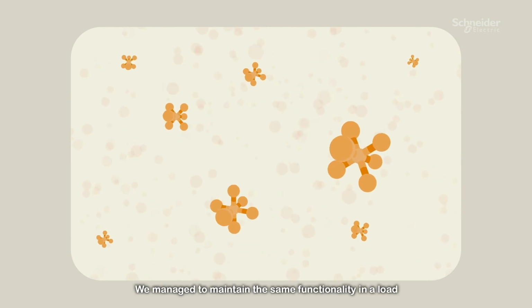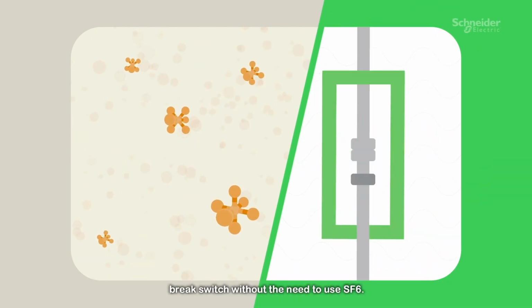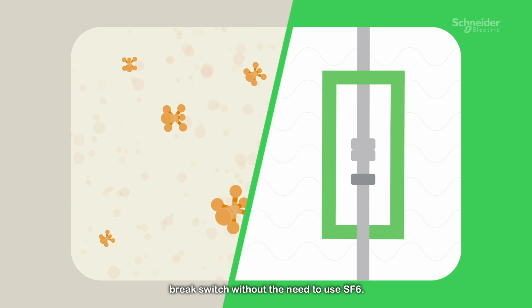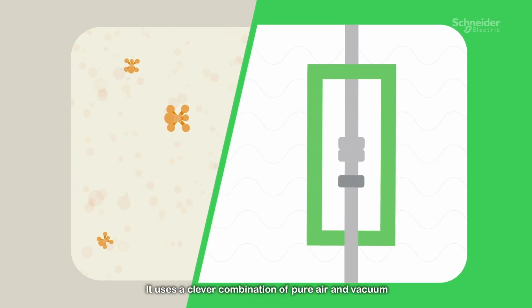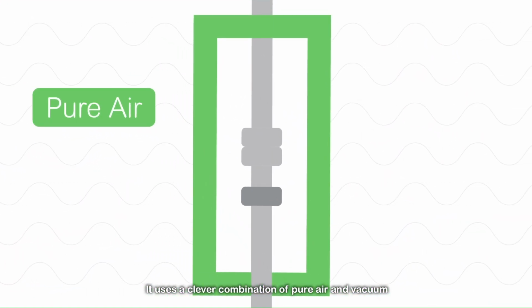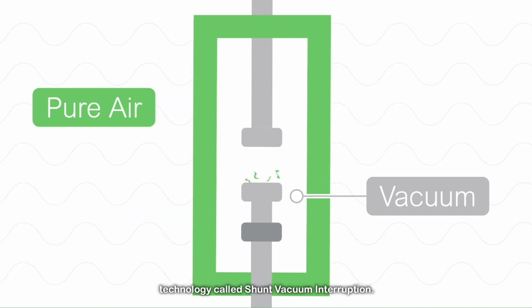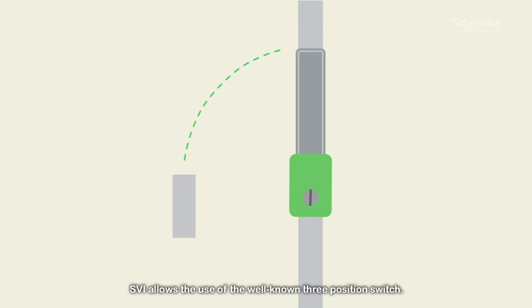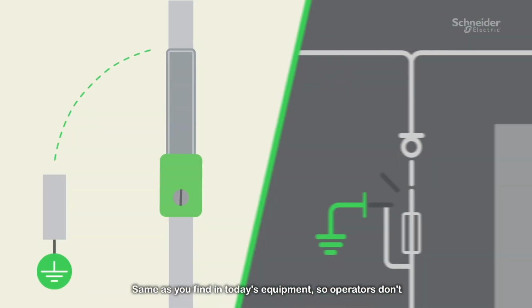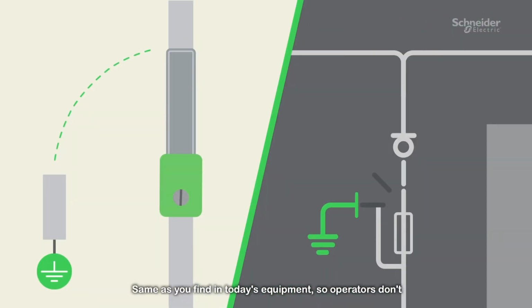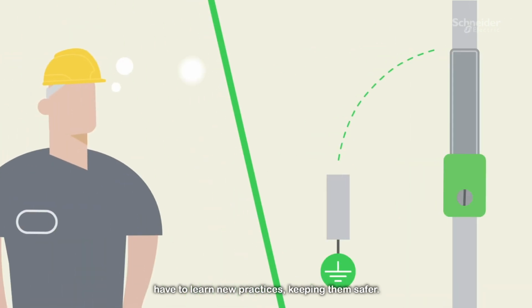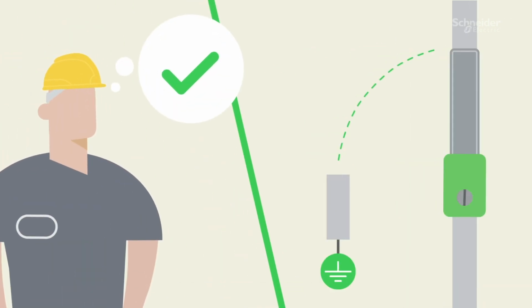We managed to maintain the same functionality in a load break switch without the need to use SF6. It uses a clever combination of pure air and vacuum technology called shunt vacuum interruption. SVI allows the use of the well-known 3-position switch, same as you find in today's equipment, so operators don't have to learn new practices, keeping them safer.